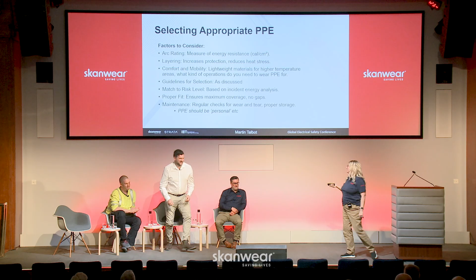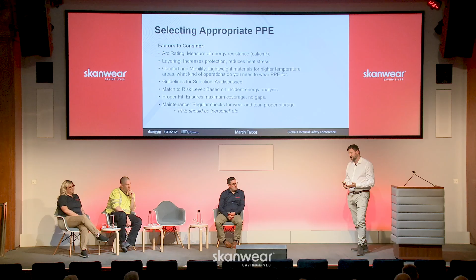Moving back, what I was talking about before is having an incident energy analysis, or an arc flash study. From that you'll get the arc rating of your equipment, and it's all in the same format. That study tells you the incident energy in cal per centimetre squared, and the PPE is rated in cal per centimetre squared as well.